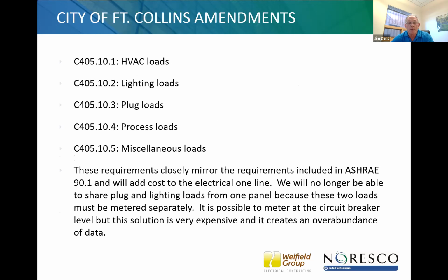So HVAC loads, lighting loads, plug loads, process loads, and miscellaneous loads will all have to be metered separately, and that's going to cost you some money. Your one line is going to have to be built in such a way that your HVAC loads are fed separately from your lighting loads, and that's separate from your plug loads. So your one lines and your panels and that kind of stuff in Fort Collins are going to be more expensive than you would see in other jurisdictions.